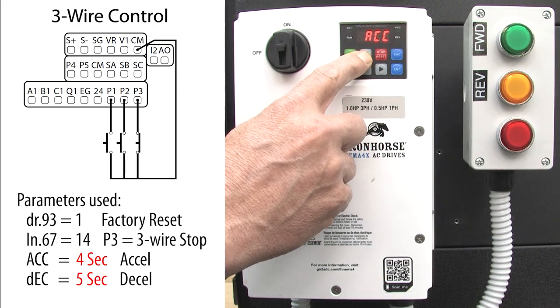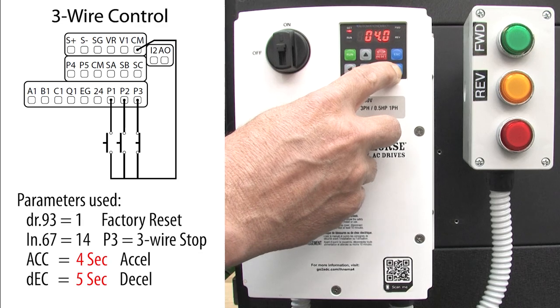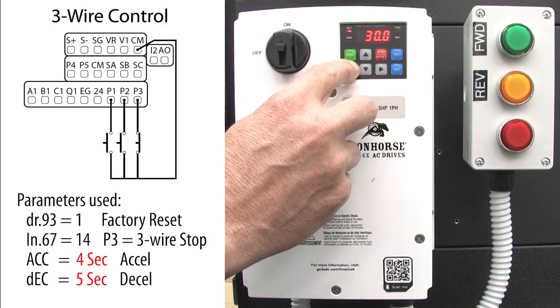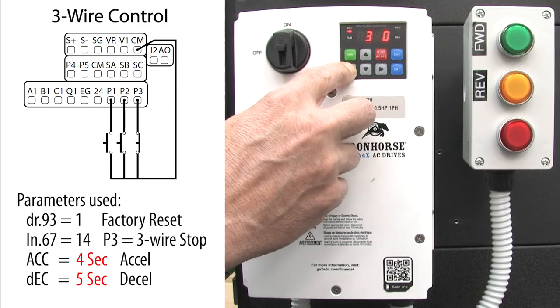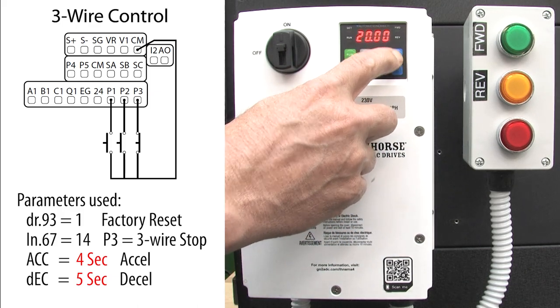Up arrow to the acceleration parameter, enter to accept, change it to something shorter. Enter to select, enter to accept. Up arrow to the deceleration, enter to select. I'll change that to something a lot shorter, enter to select and enter to accept. And escape back to the top level frequency display.